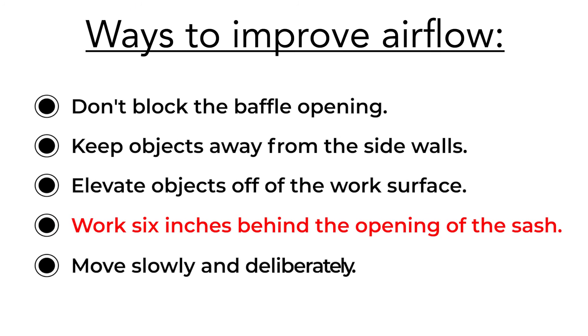Work six inches behind the sash to prevent chemicals from being drawn out. Move slowly and deliberately within the hood and when you remove objects. All of these things must be adhered to for the fume hood to have a chance of keeping you and your colleagues safe.